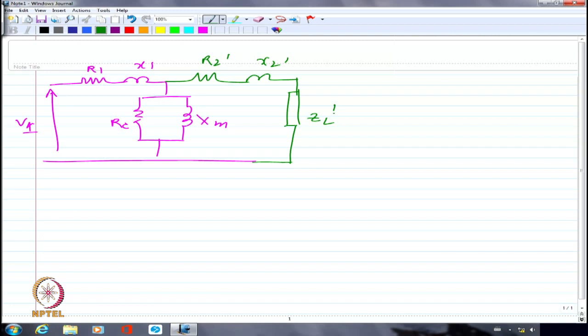We wanted to first of all determine all the parameters of this equivalent circuit, which can be done by two tests. We said that actually loading the transformer is going to be difficult because we would end up wasting a huge amount of power, and it will be very difficult for us to find the load which can withstand the rated current or rated power. That's the reason we would like to determine the parameters by creating situations like applying rated voltage without really passing rated current, and the second situation, passing rated current whereas applying only a fraction of the rated voltage. So we are not really loading the transformer to the fullest extent, neither by the current nor by the voltage. That's what we are trying to do.